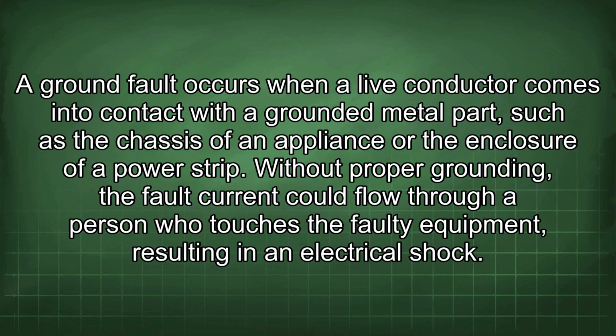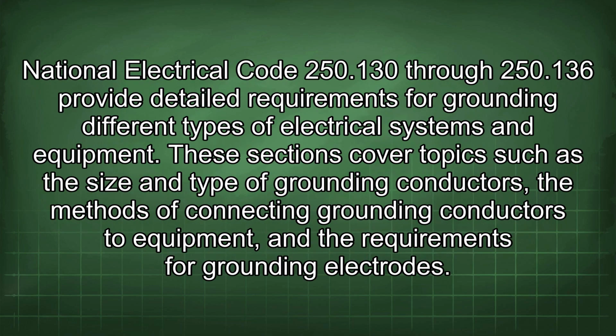A ground fault occurs when a live conductor comes into contact with a grounded metal part, such as the chassis of an appliance or the enclosure of a power strip. Without proper grounding, the fault current could flow through a person who touches the faulty equipment, resulting in an electrical shock. National Electrical Code 250.130 through 250.136 provide detailed requirements for grounding different types of electrical systems and equipment.